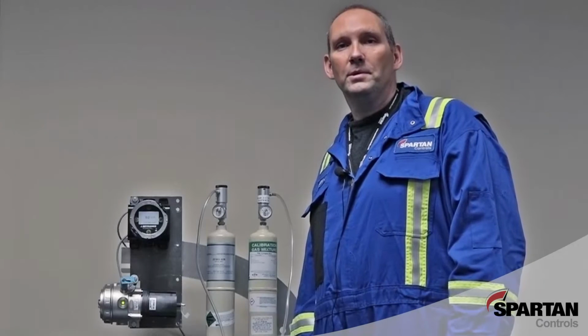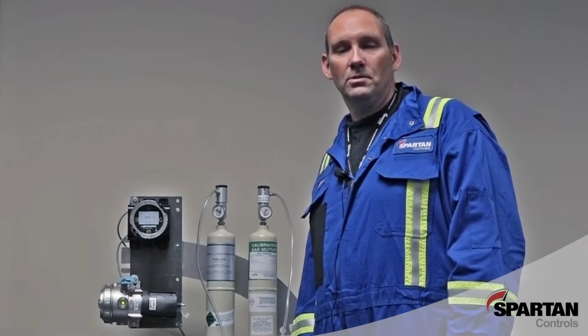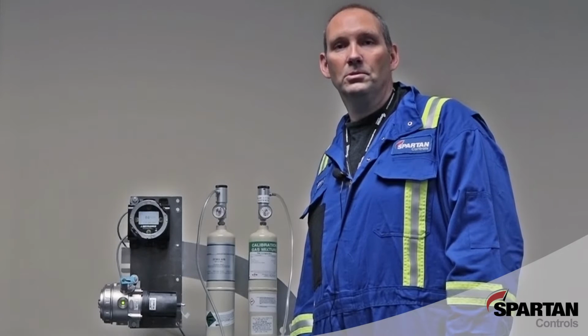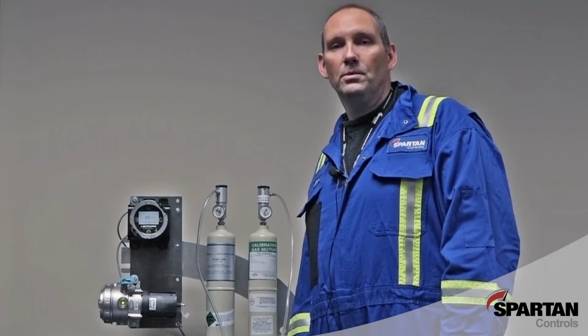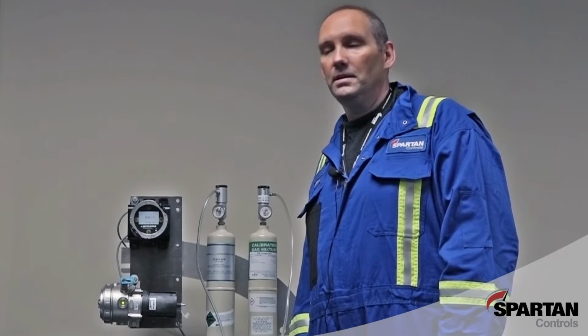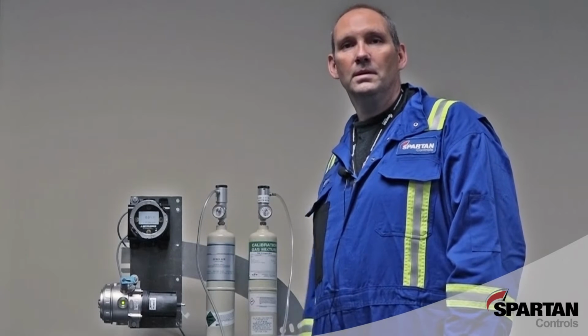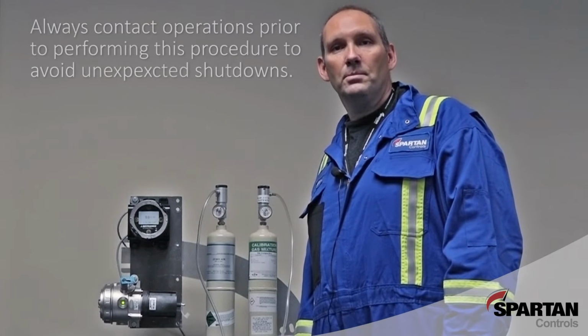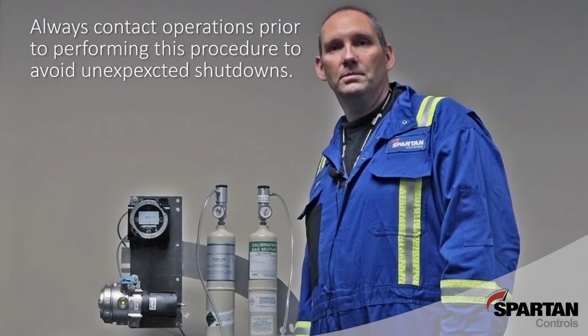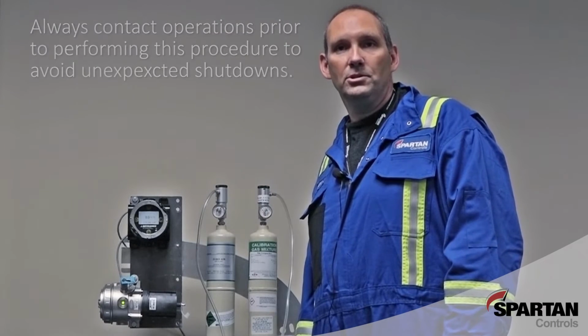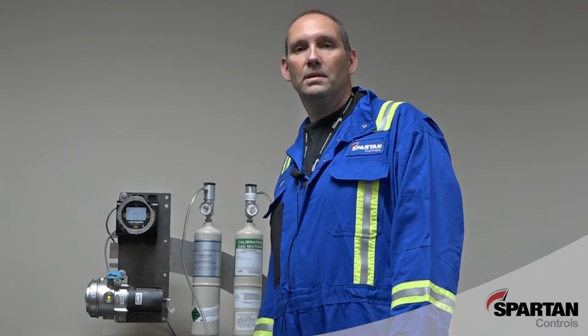In this video, we'll demonstrate the calibration procedure for the Det-Tronics PointWatch gas detector, also known as the Eclipse, through the use of the Det-Tronics UD10 universal display. Please ensure you contact your operations room prior to doing this procedure, as you wouldn't want to cause any unexpected shutdowns. For the purpose of expediency, I've taken the liberty of wiring the devices and powering them up.